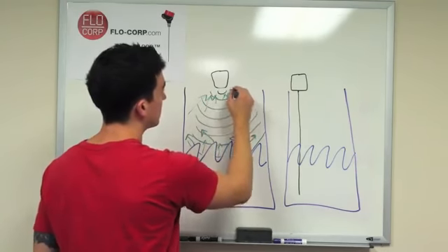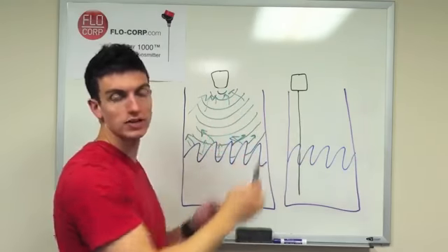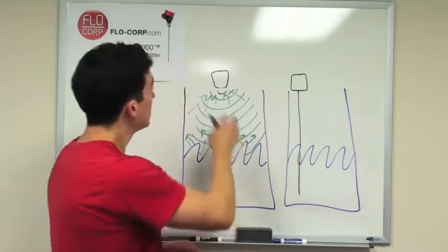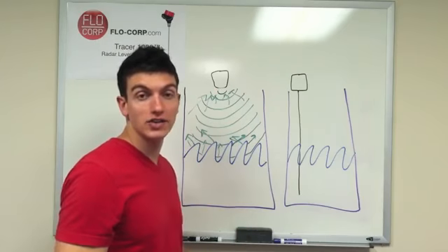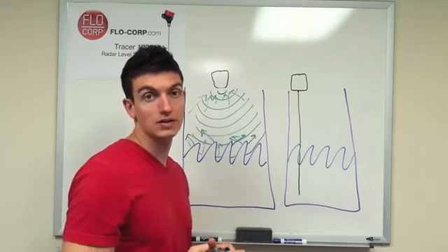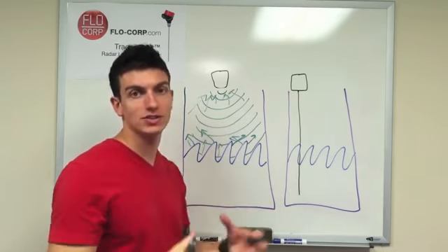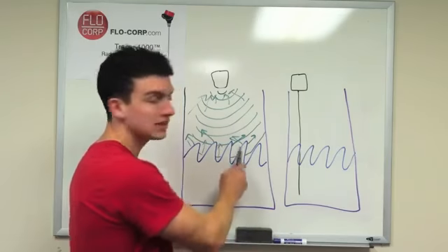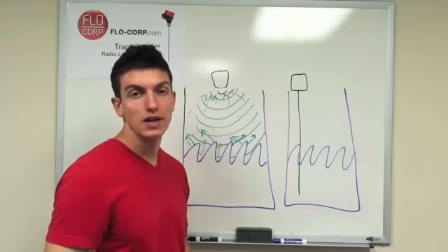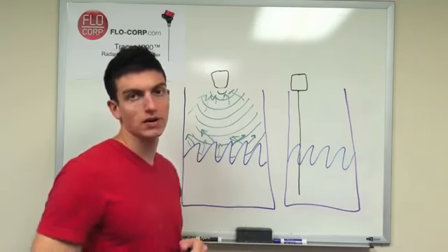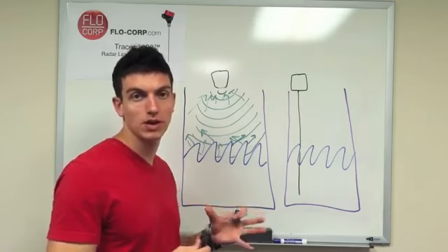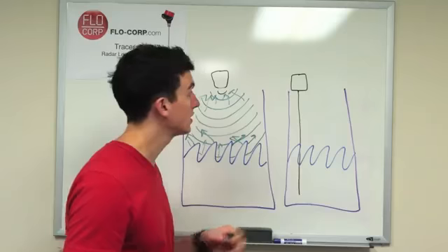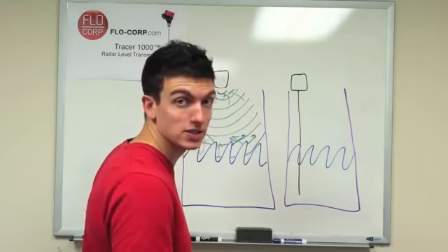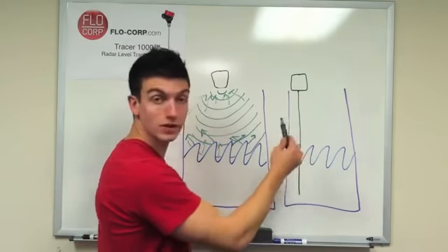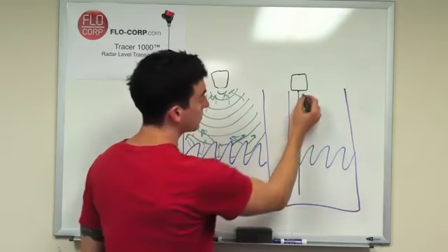And what we're going to get up here is just echoes coming in from every direction. Now, ultrasonic level meters are designed with some algorithms that should factor some of this stuff out, but this can give you a problematic reading. This is one situation where radar becomes a little superior to the ultrasonic.